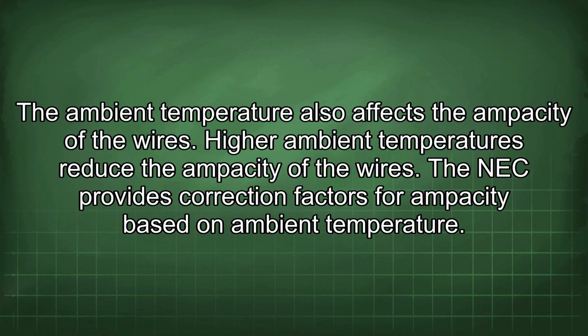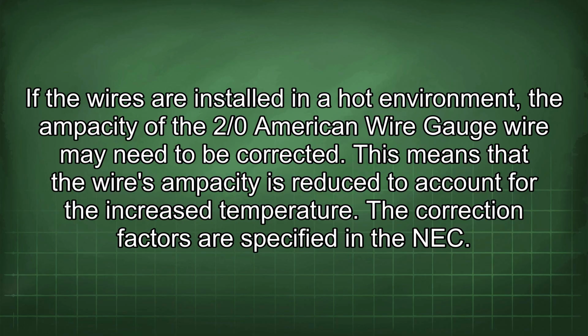The ambient temperature also affects the ampacity of the wires. Higher ambient temperatures reduce the ampacity of the wires. The NEC provides correction factors for ampacity based on ambient temperature. If the wires are installed in a hot environment, the ampacity of the 2/0 American wire gauge wire may need to be corrected. This means that the wire's ampacity is reduced to account for the increased temperature. The correction factors are specified in the NEC.